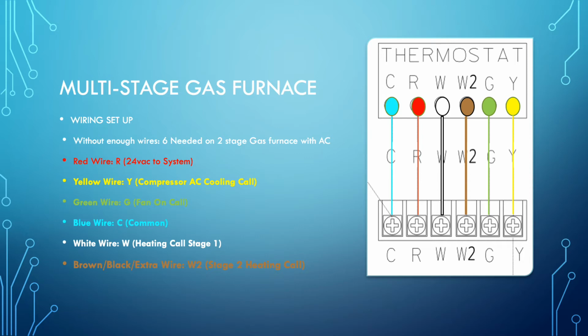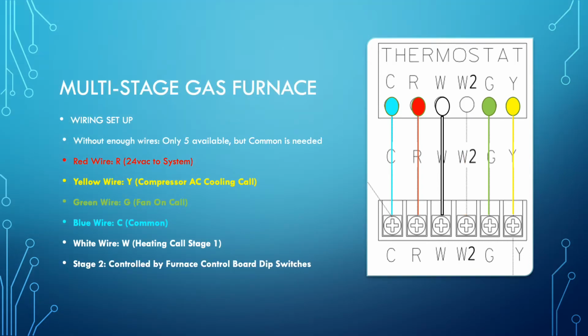Now, not all systems have it. Some customers want a 2-stage high efficiency furnace, but they do not have 6 wires. In fact, they only have 5 wires, but they also need the common. So there is a solution to this, particularly with the Rheem two-stage gas furnace. However, other brands generally have the same option also, and this is controlling it with dip switches at the control board.